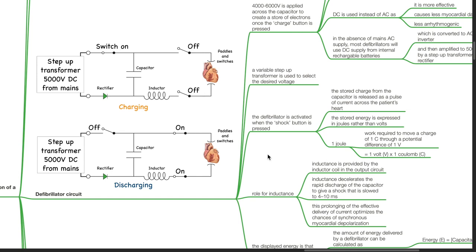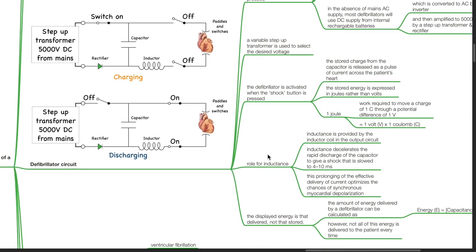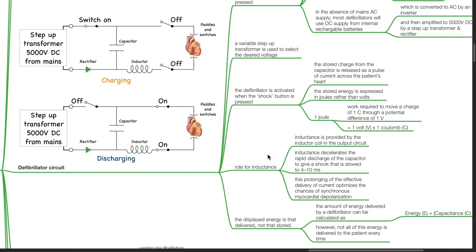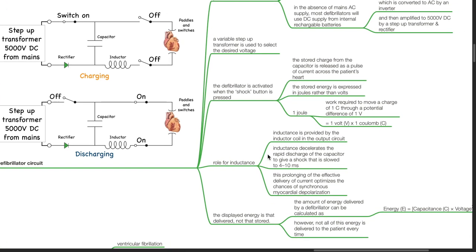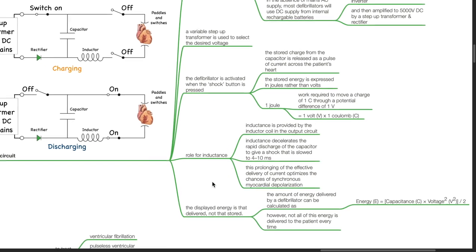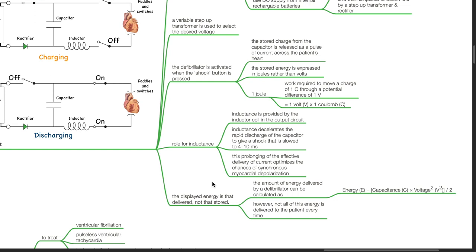The stored energy is expressed in joules rather than volts. One joule equals the work required to move a charge of one coulomb through a potential difference of one volt, or one volt times one coulomb. The role of inductance: inductance is provided by the inductor coil in the output circuit. Inductance decelerates the rapid discharge of the capacitor to give a shock slowed to 4 to 10 milliseconds, optimizing synchronous myocardial depolarization. The energy delivered can be calculated as E = C × V² / 2.